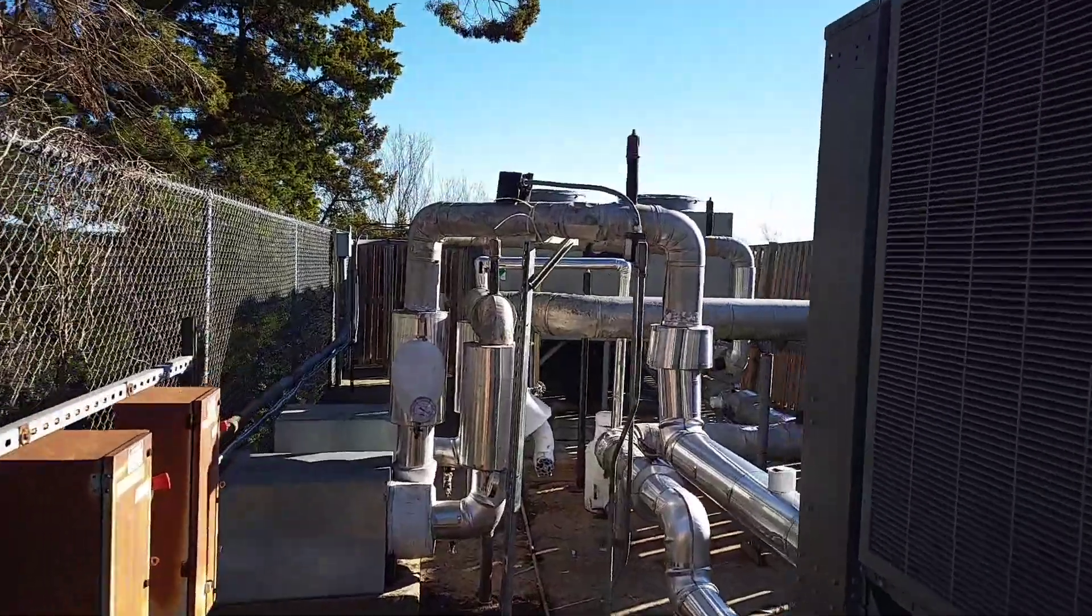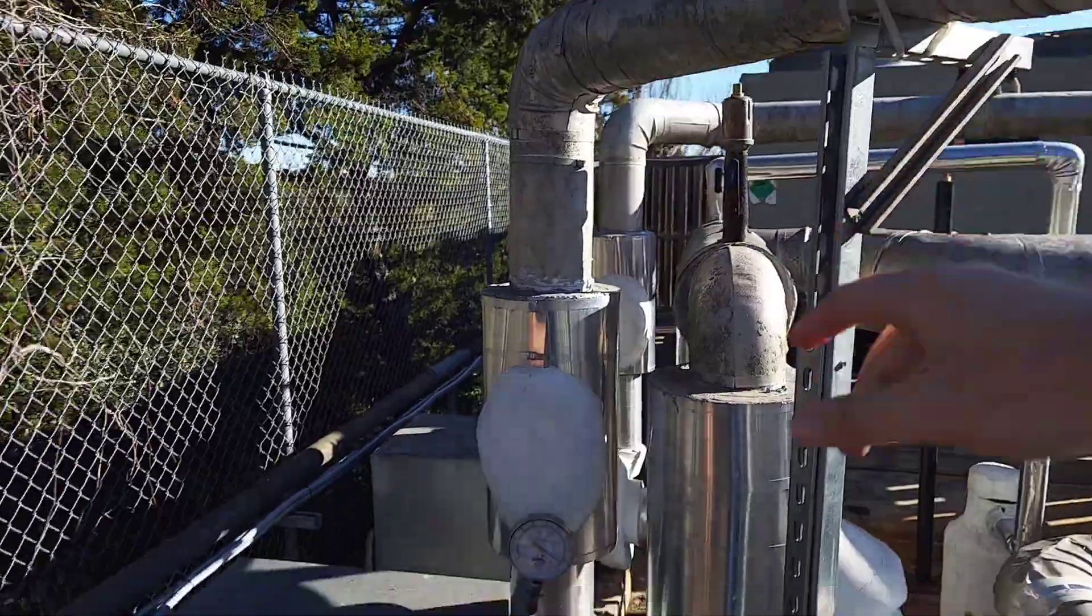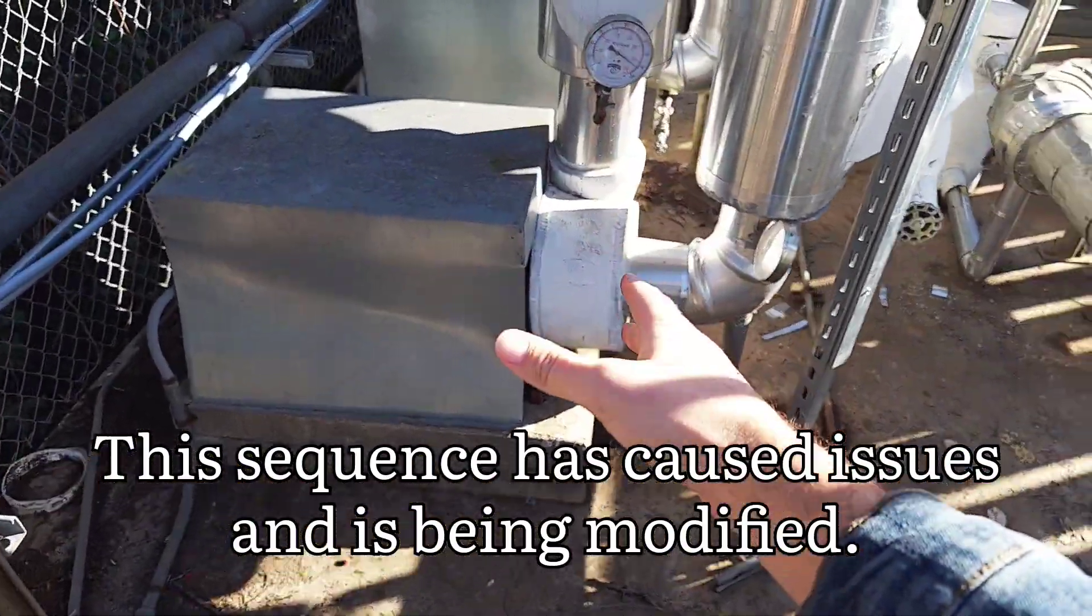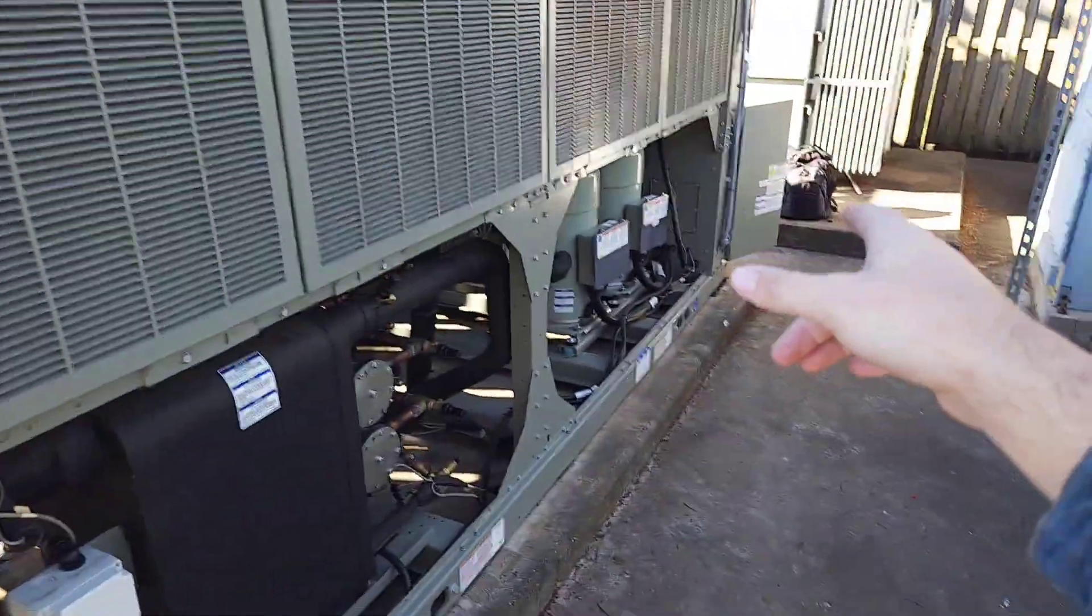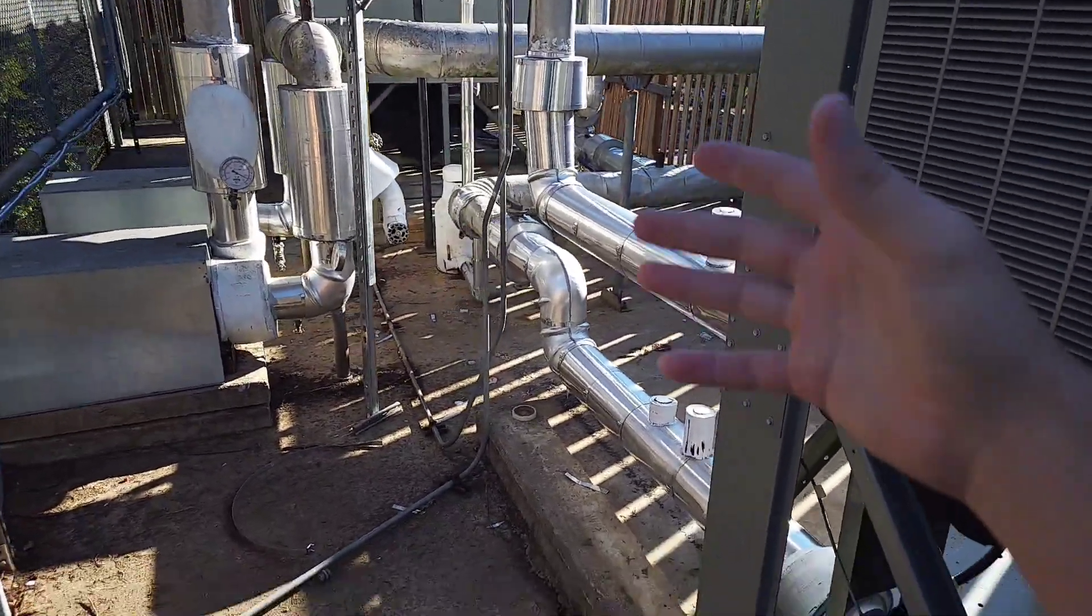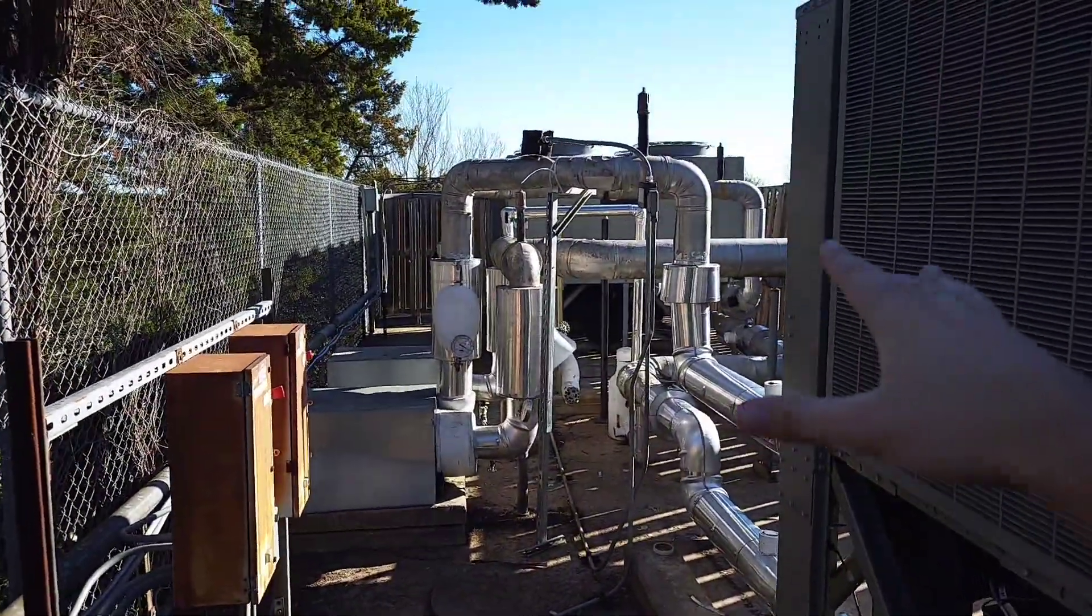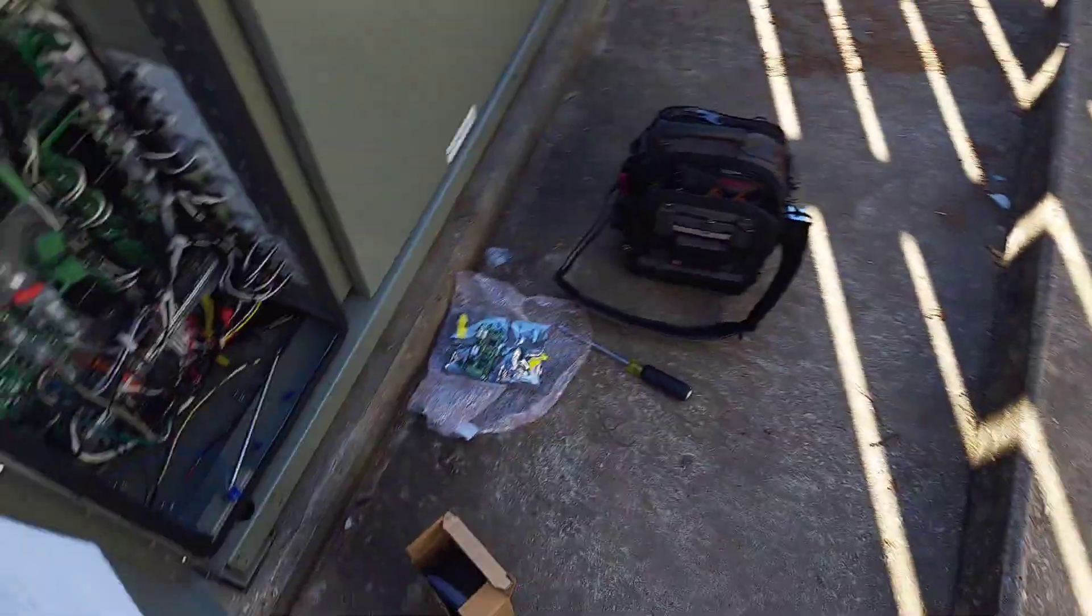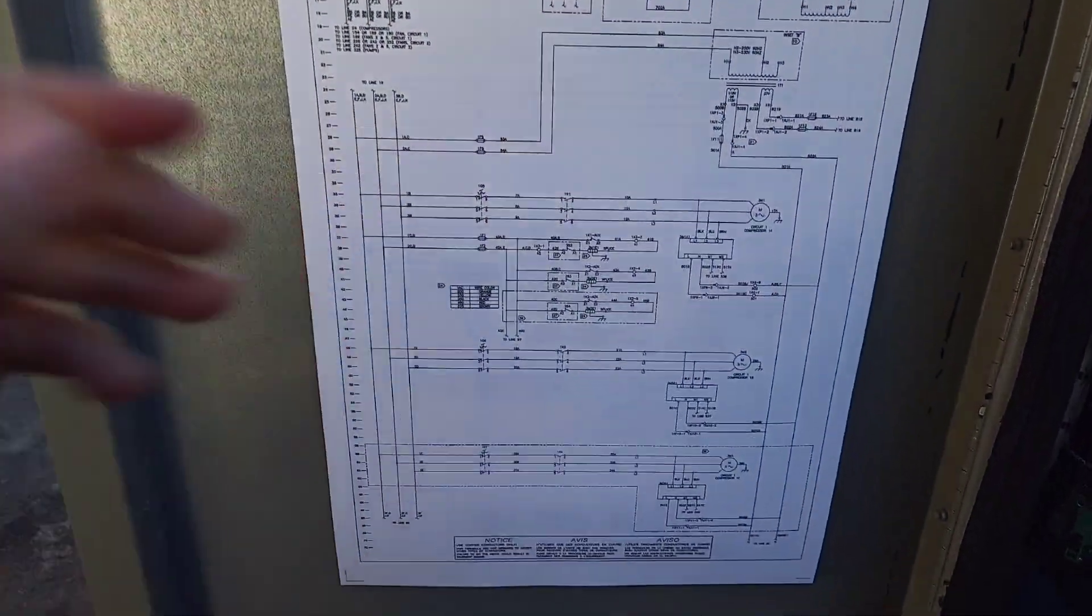We also just replaced this flow switch. This one had gone bad, so we put a new seal tight and got a new flow switch in. This functions as the start-stop for the chiller. What the automation system does is it fires this pump. When the pump fires through a relay, it closes that paddle switch, and that paddle switch closes the start-stop circuit for the chiller. The old sensor was just stuck in a closed position, so that pump wouldn't even have to be on and it was closing, which causes alarms and issues with this particular chiller.